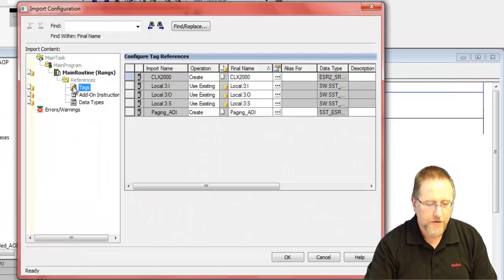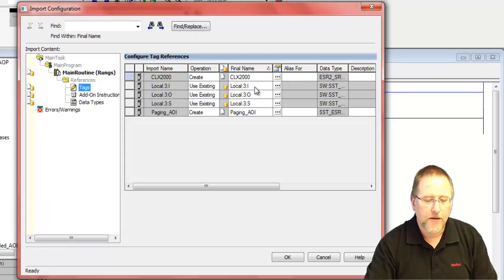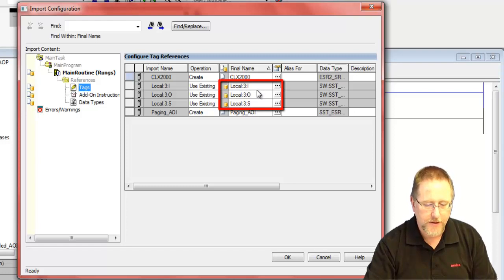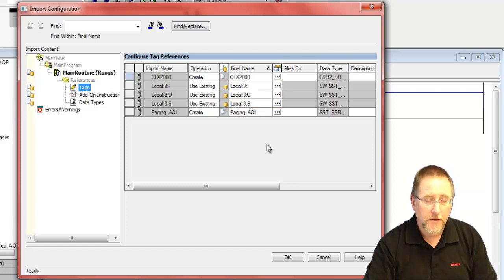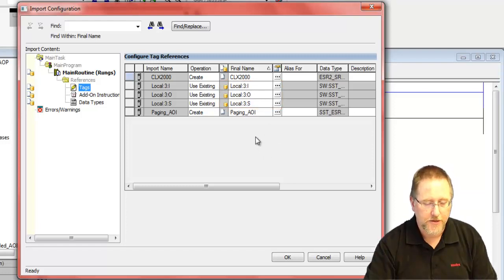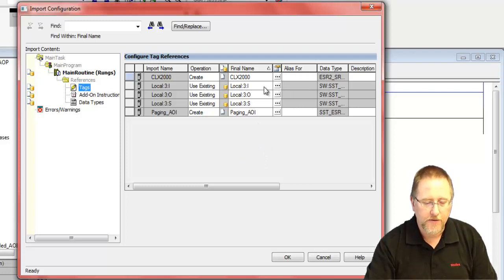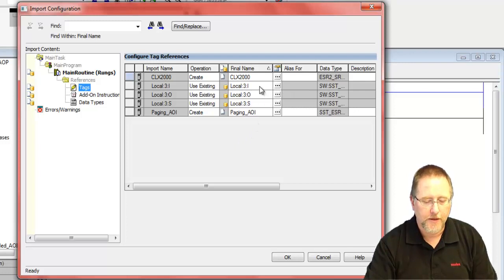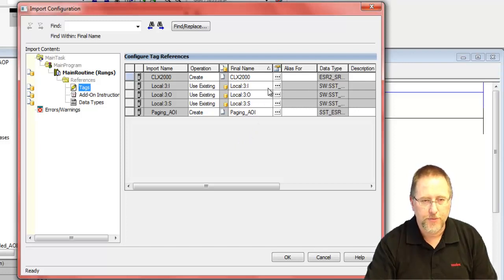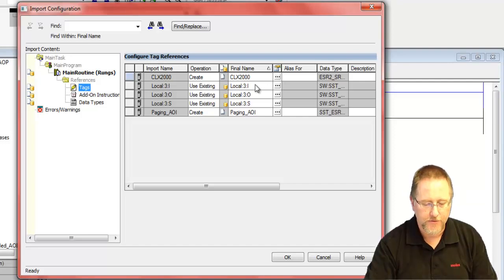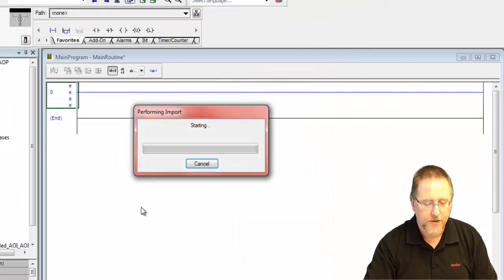Now click on tags here and you'll see that it assumes that the module is in slot 3, which is what I've done here. If you can, it's best to put the module in slot 3 because you don't have to make any changes. But if you have to have a different slot, then what you need to do after you've added your module and imported the add-on instruction is come here and choose the proper tags and slot number for the module. So, since we're okay, we'll just press the okay button.